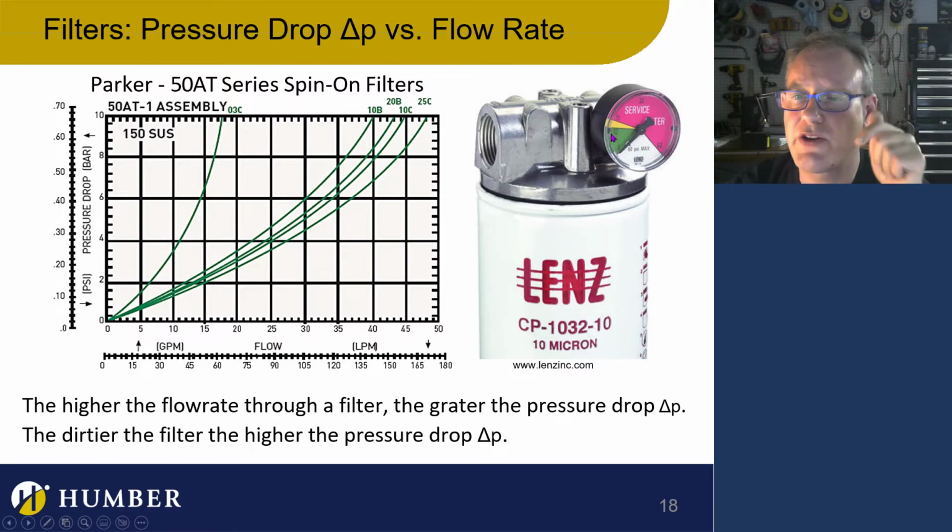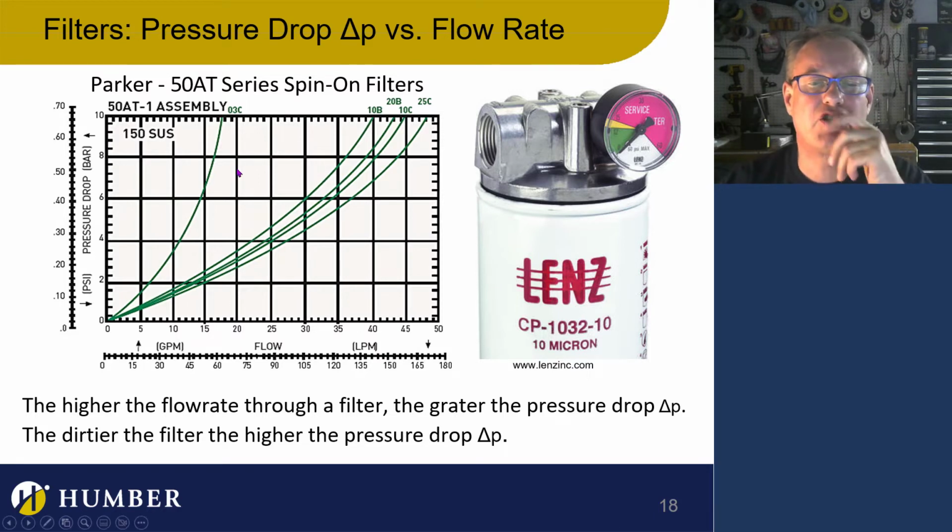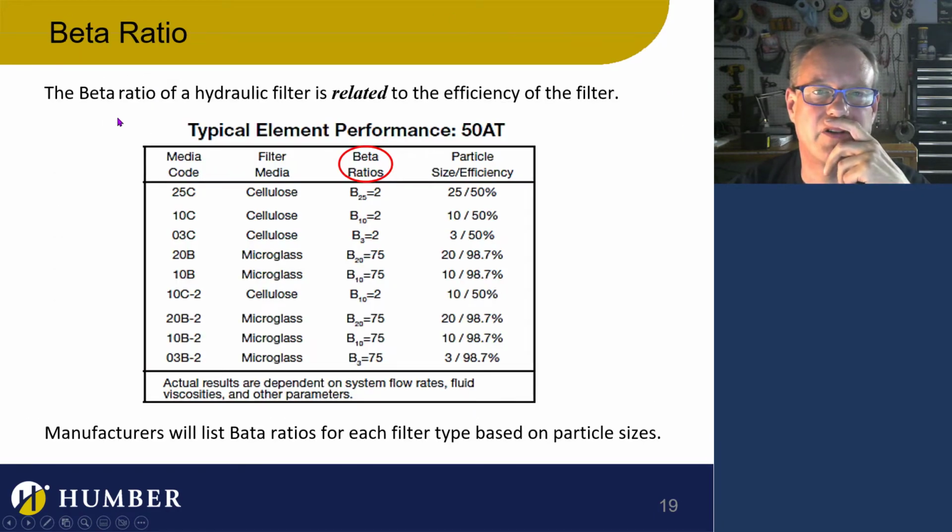I want to tell you guys that this is important, that on our external filters, you're going to see this. And if it gets into the yellow, that's it. If it gets even close to the yellow, change it. Dude, it's like a $20 filter. Whatever, it's going to save you thousands of dollars by changing that regularly. Again, it's the first line of defense. It's huge. So make sure you keep an eye on those things and never let them even get into the yellow. It's absolutely crucial that you don't do that.